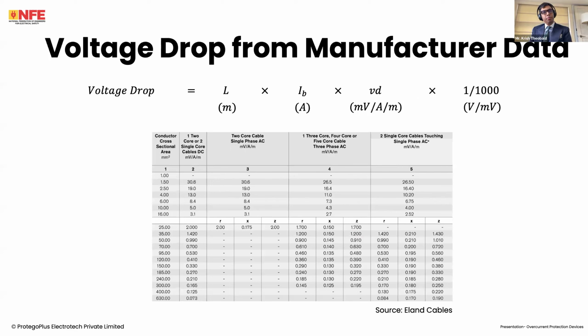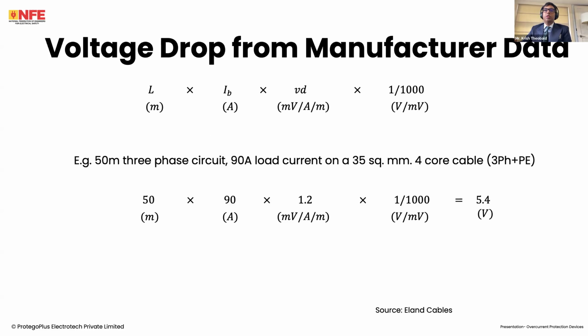Let us consider a situation: 35 square mm, four core cable. Z is the total impedance value, 1.2 millivolts per amp per meter, like I just mentioned here. So for a 50 meter three phase circuit, if we are considering 35 square mm conductor, 90 amp load current on a four core, 50 meters times 90 amps times 1.2 millivolts per amp per meter, which we convert from millivolts to volts, we get 5.4 volts. This is how we calculate volt drop from manufacturer data.